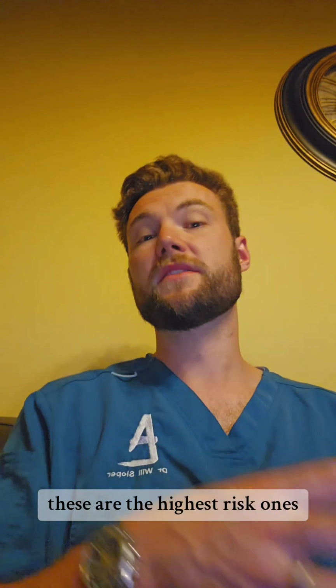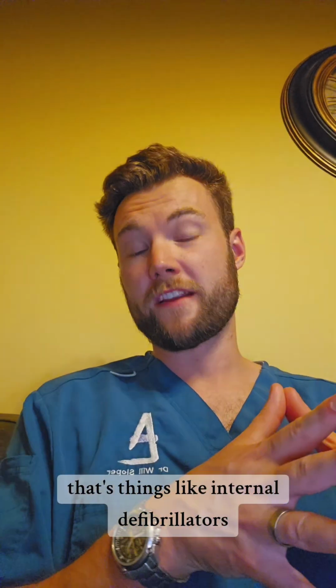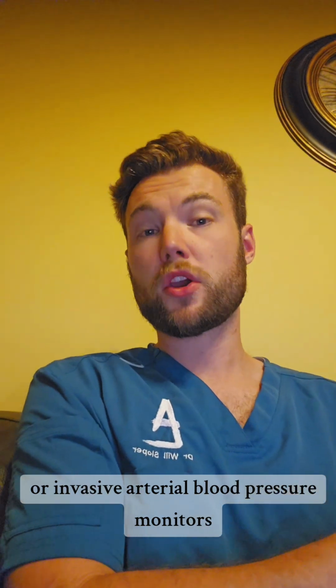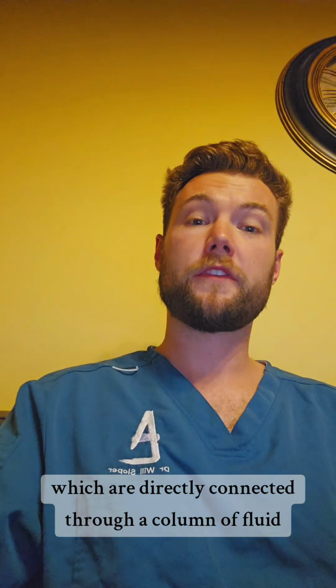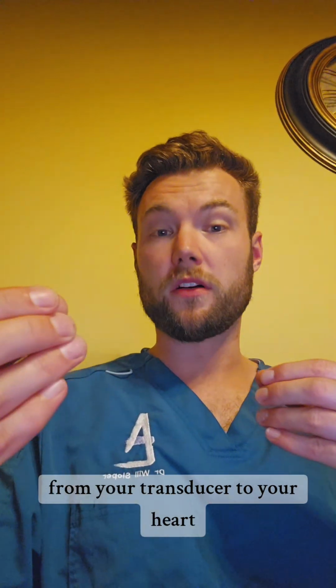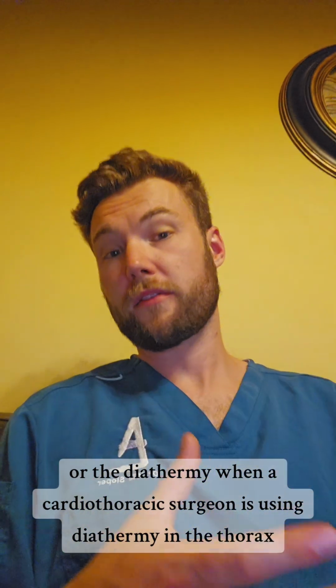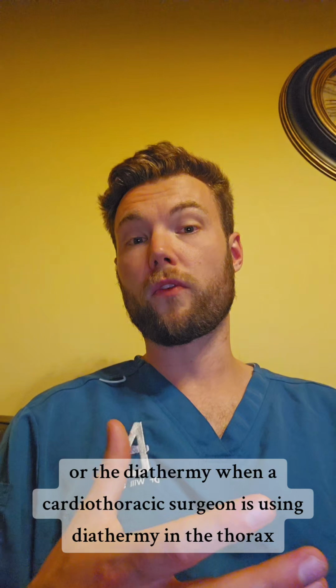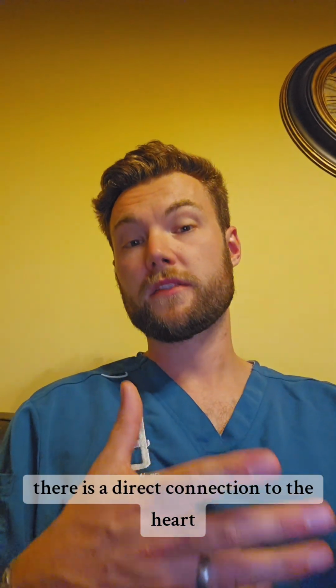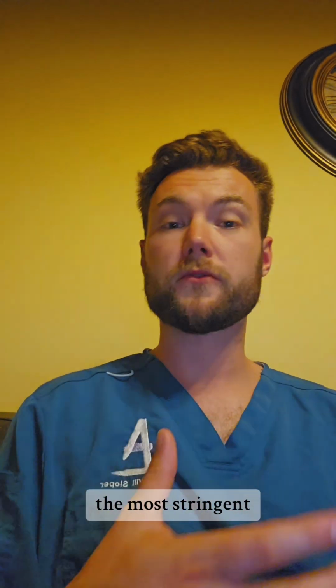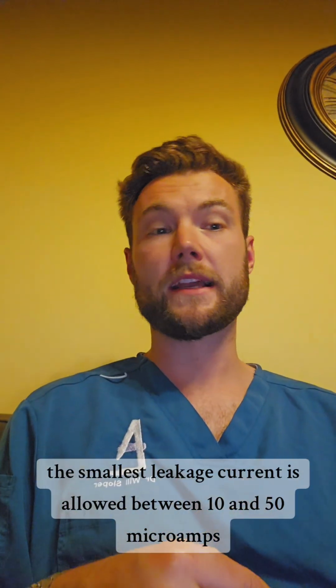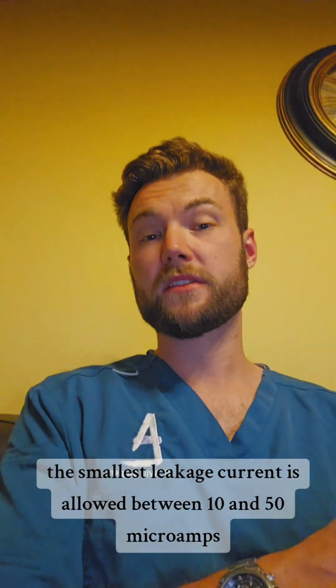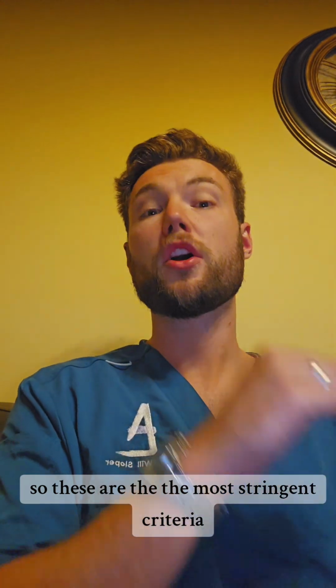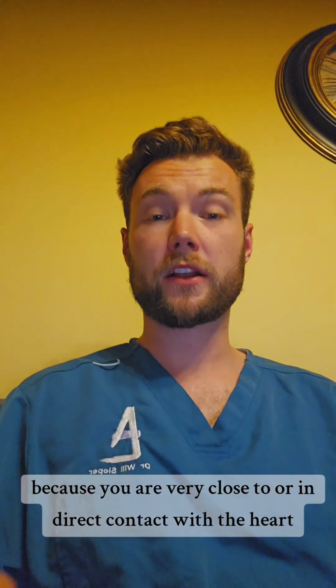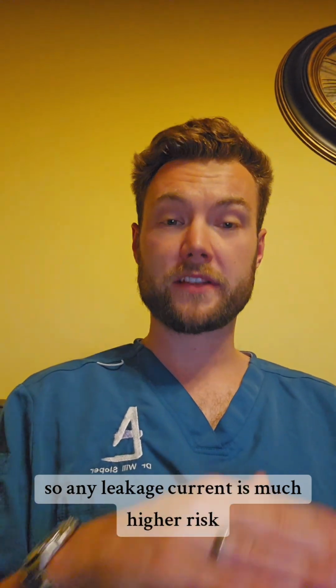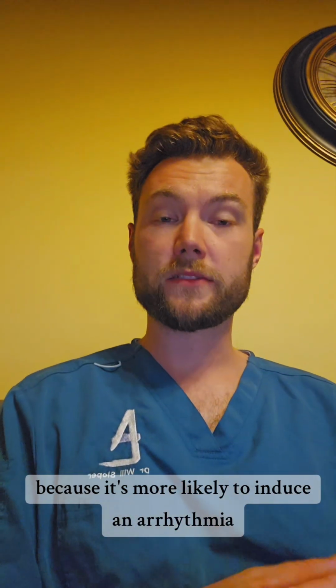These are the highest risk ones. There's things like internal defibrillators or invasive arterial blood pressure monitors, which are directly connected through a column of fluid from your transducer to your heart. Or the diathermy, when a cardiothoracic surgeon is using diathermy in the thorax, there is a direct connection to the heart. So these are the highest risk, the most stringent. The smallest leakage current is allowed, between 10 and 50 microamps. So these are the most stringent criteria because you are very close to or in direct contact with the heart. So any leakage current is much higher risk because it's more likely to induce an arrhythmia.